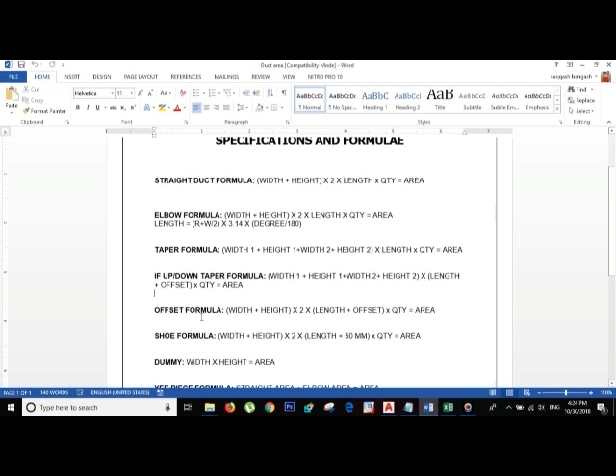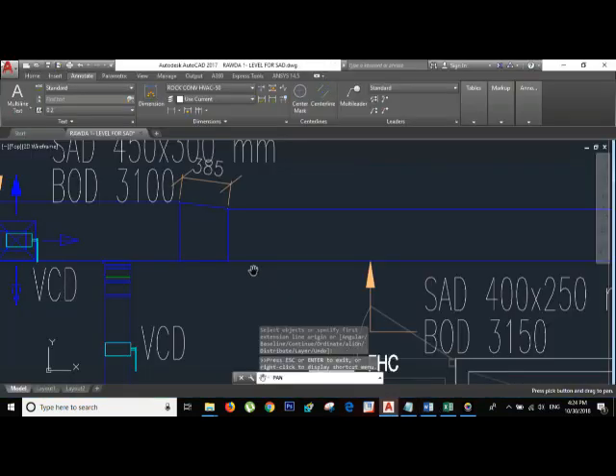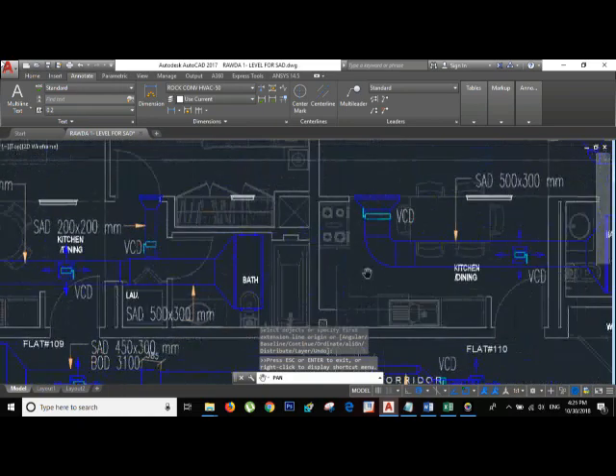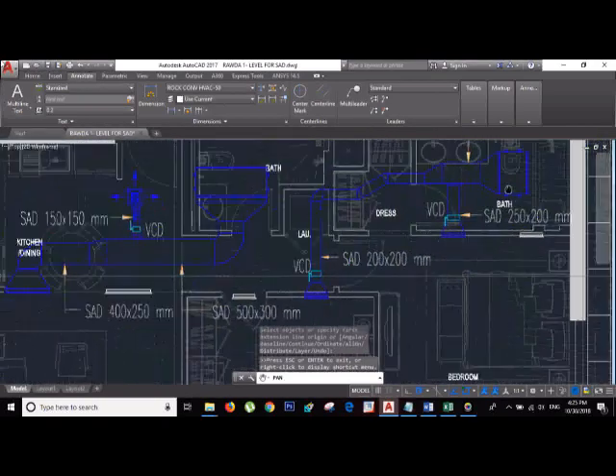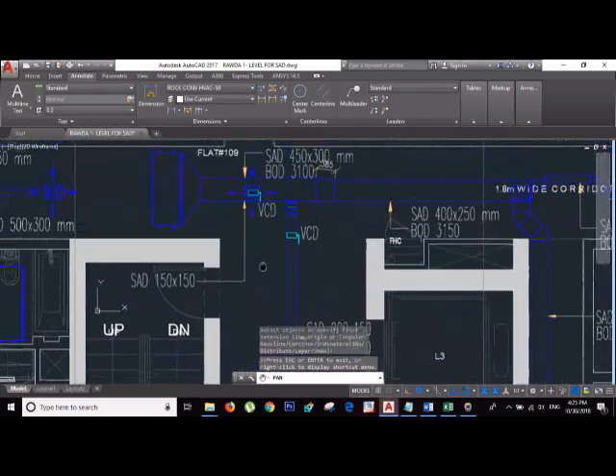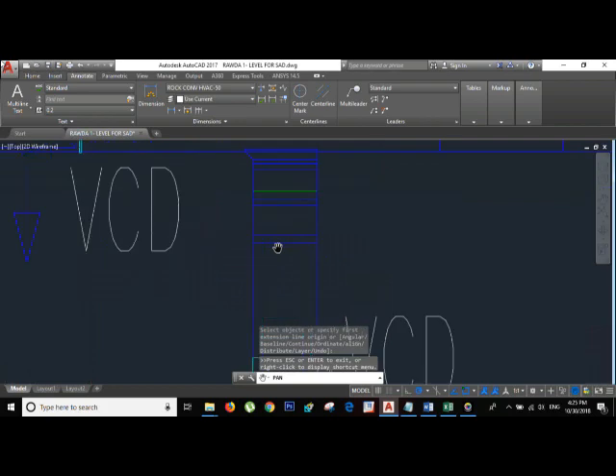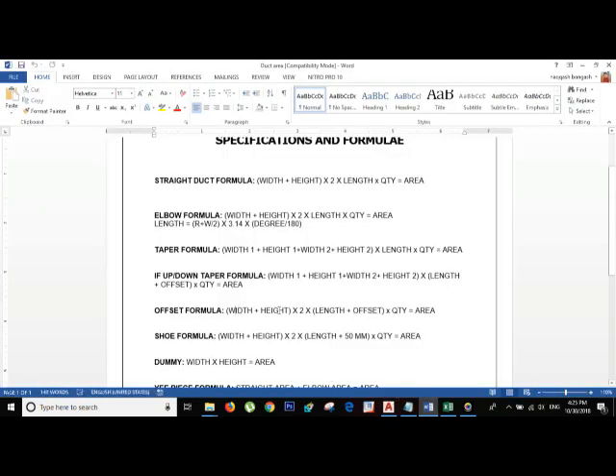Now for the offset duct formula — it's actually the same as a straight duct formula, but you need the offset length. For example, if the duct is down 200 mm, you need the width plus height of the offset — say 450 mm by 550 mm — put it in, multiply by 2, then multiply by the length plus the offset distance added together.